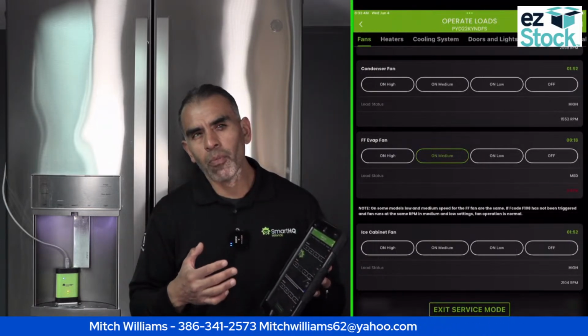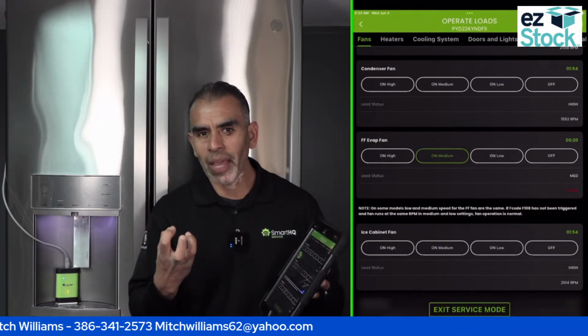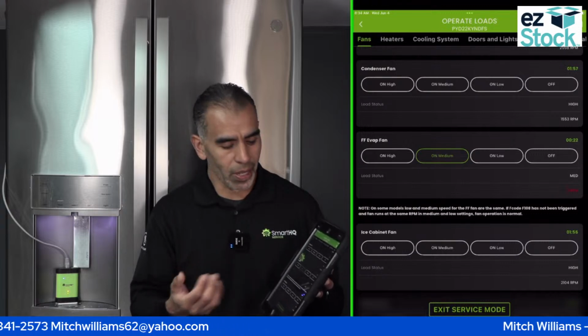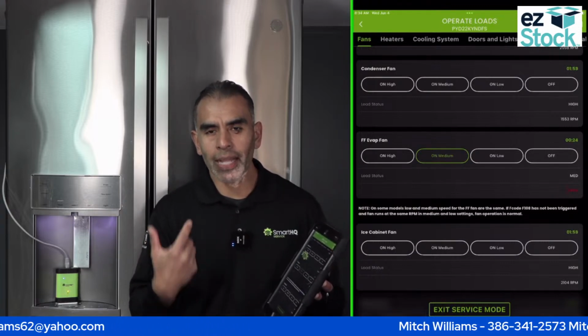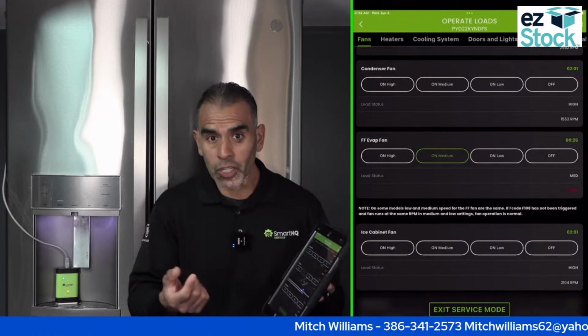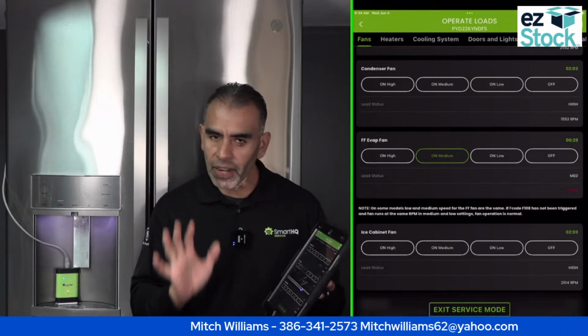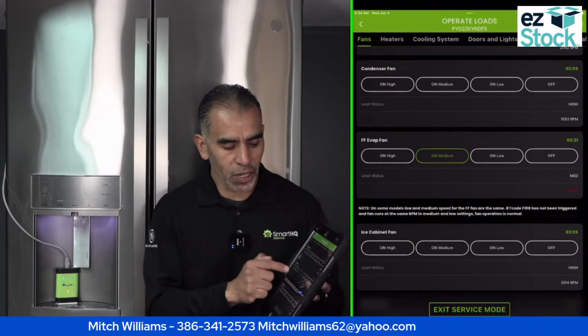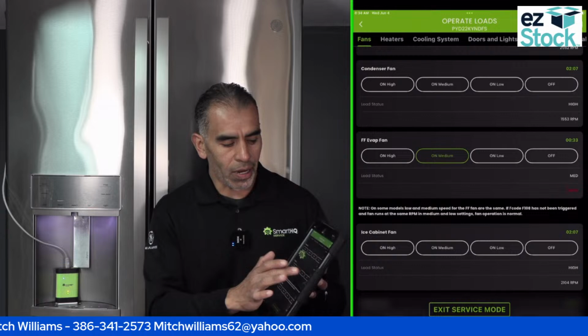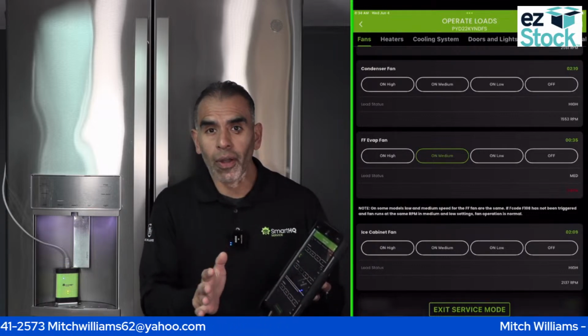Could it be a problem with some restriction, maybe ice buildup? Yeah, it could. It could also be a bad wire harness, but that's where you actually have to inspect it as a technician. But at the very least, I know for a fact, based on these readings, that my main board is good. I don't have to replace that.